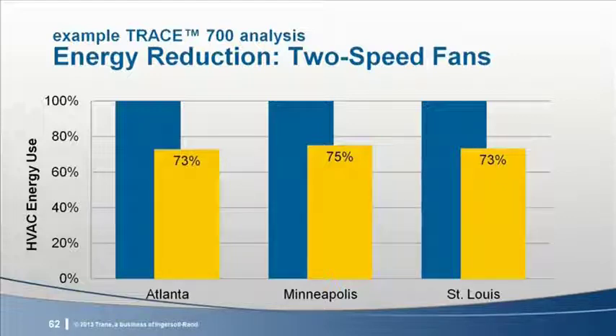The energy reduction for Minneapolis is more than one might expect when comparing two-speed fans with constant volume design heating airflow. Despite the winds of Thor blowing cold, there are mostly cooling loads because of the high internal loads of the simulated spaces. In buildings with high heating loads, we would expect more fan power consumption and less overall HVAC energy savings.